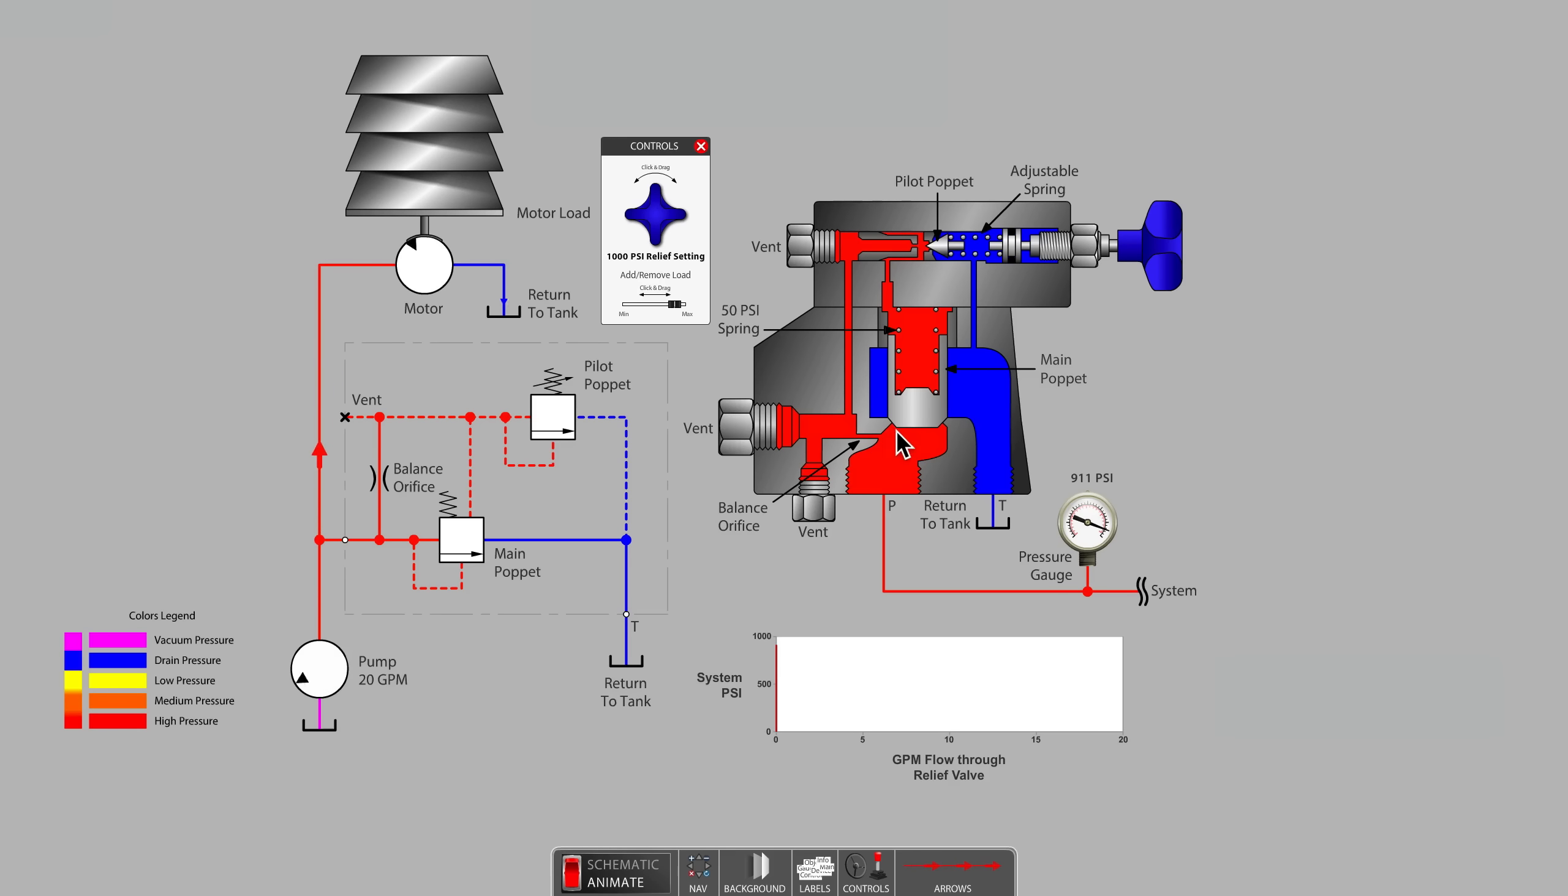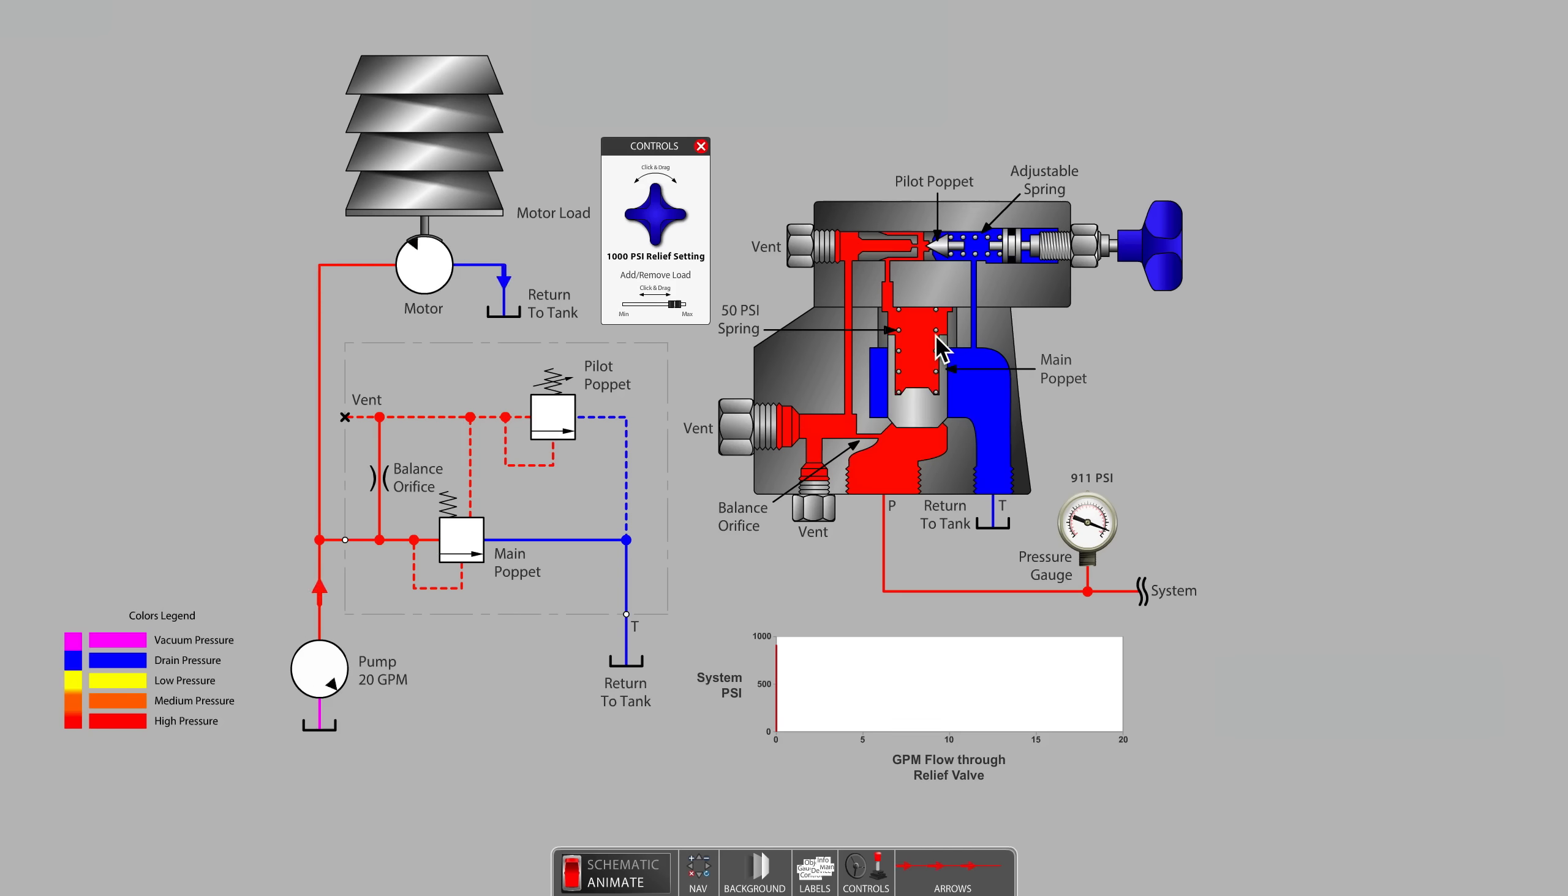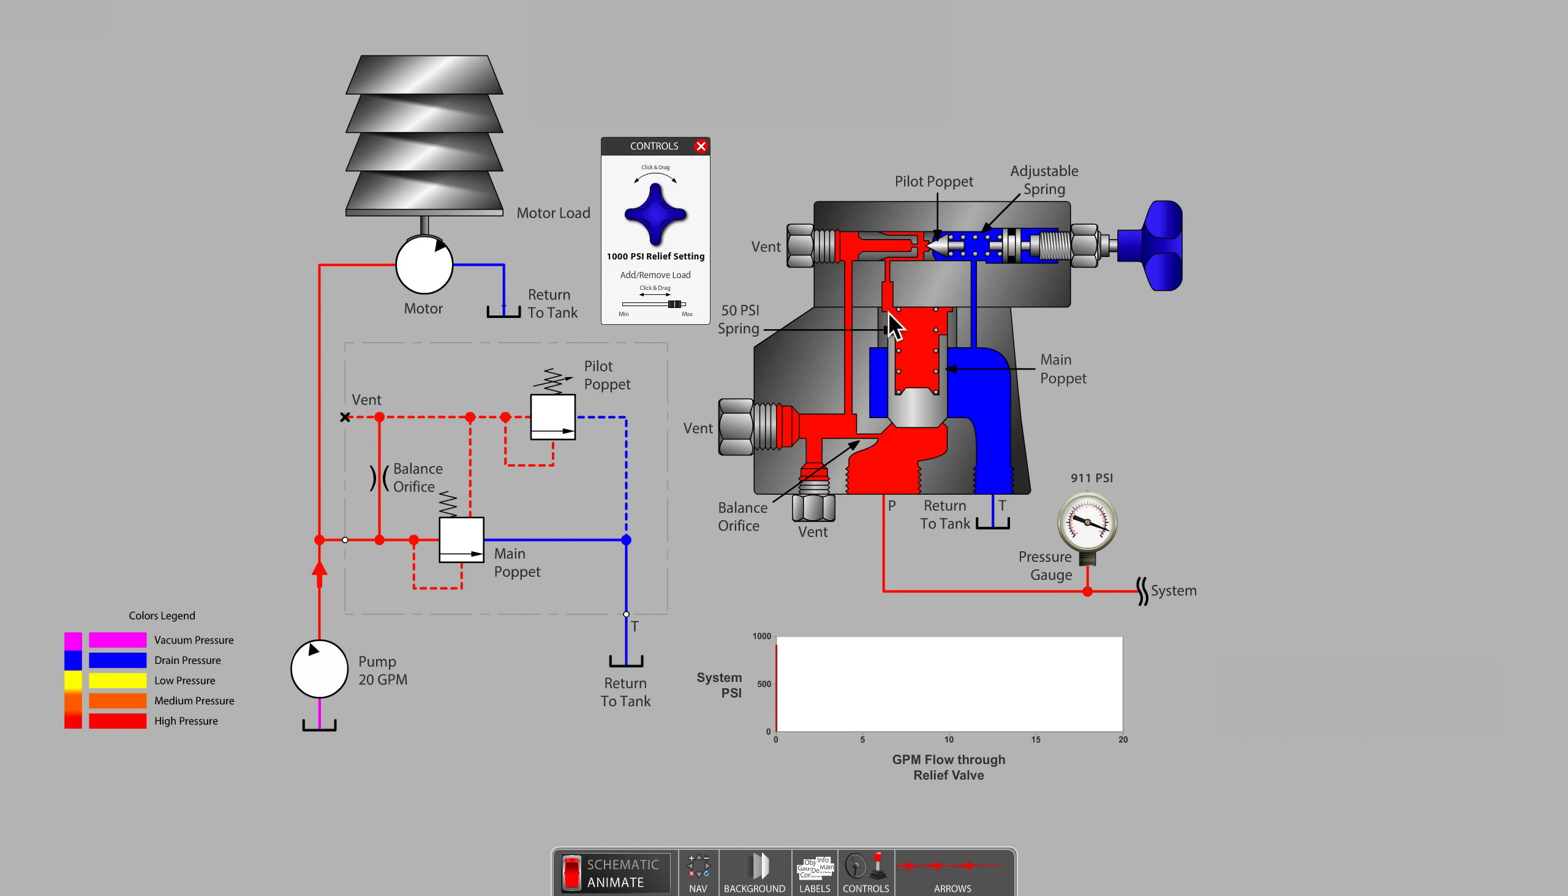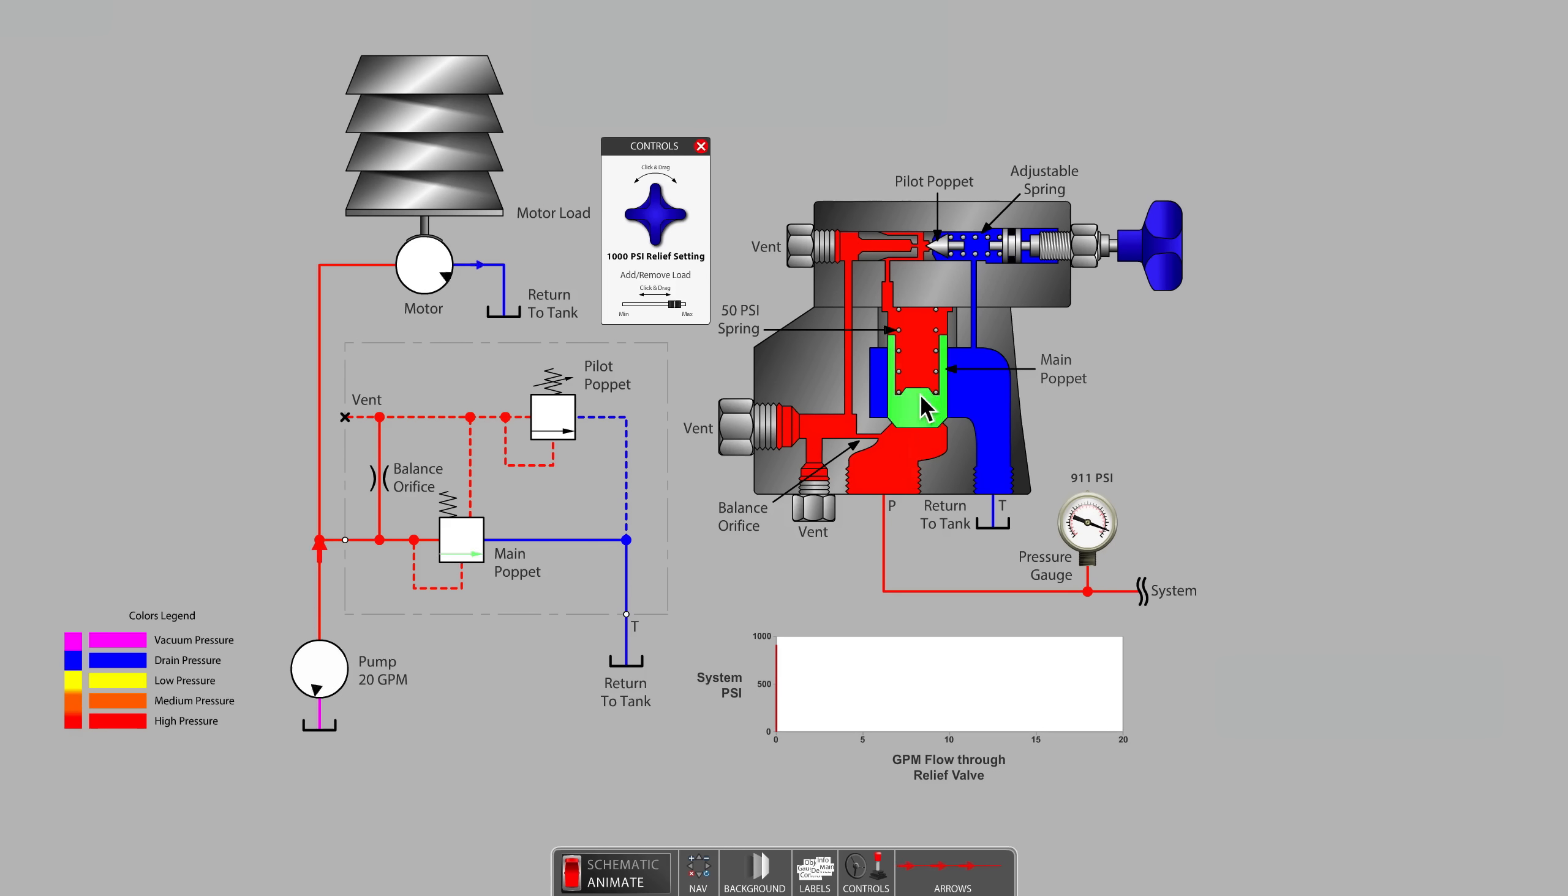Observe that the surface area on the bottom of the poppet is the same, or nearly so, as the surface area above the poppet. With an open passage from the bottom to the top of the poppet, the pressure is currently the same, both above and below. Therefore, only a weak spring is required to keep the poppet in the closed position.